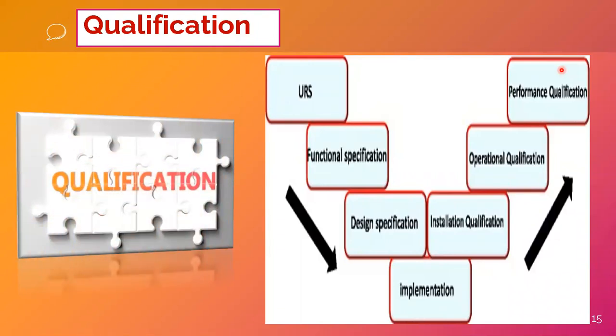Now we come to qualification. We have already discussed in a previous video what the minimum requirements are. For balance qualification, you need to prepare a URS — User Requirement Specification — and a functional specification. The URS defines the weighing range and that it must fulfill USP Chapter 41. Functional specifications can include user ID management, audit trails, password management policies, and server data storage. The design specification will be provided by the vendor, and then you proceed to installation, operation, and performance qualification.